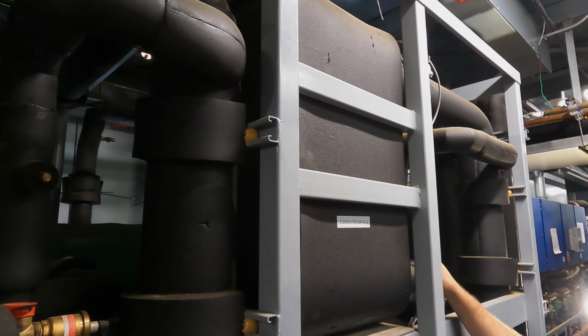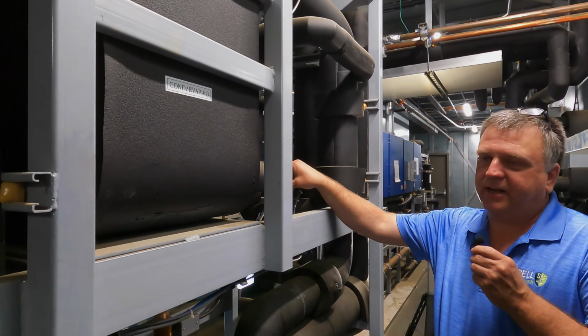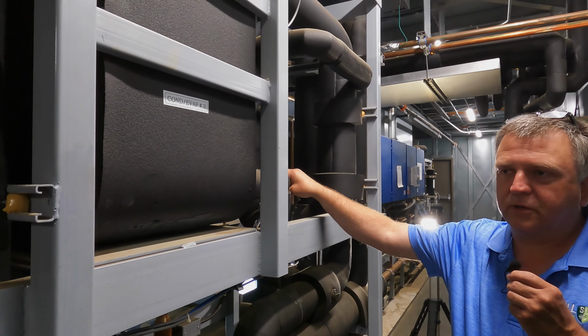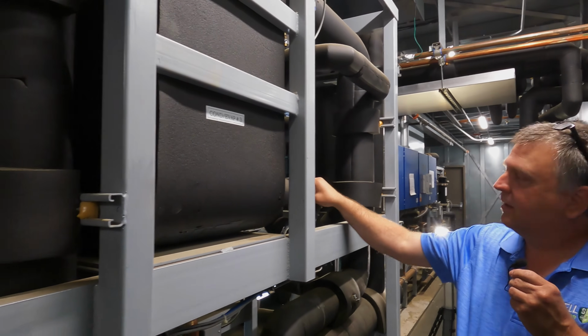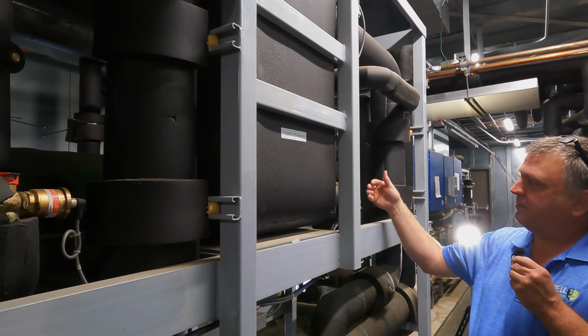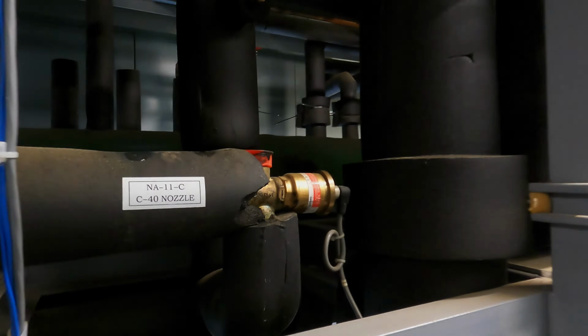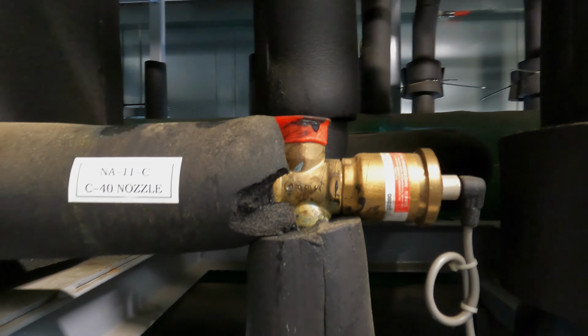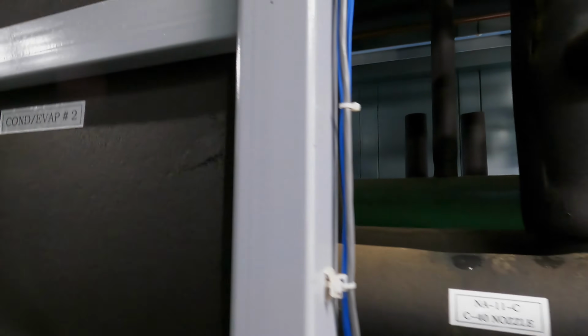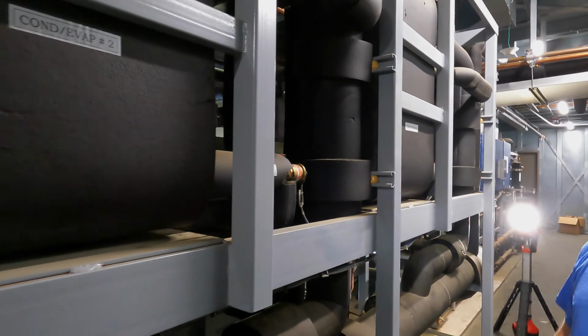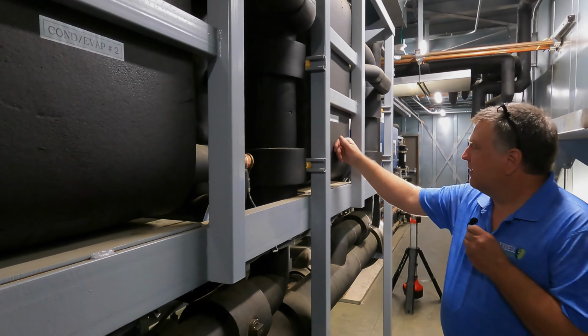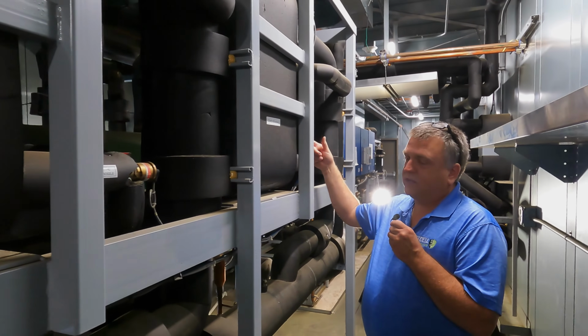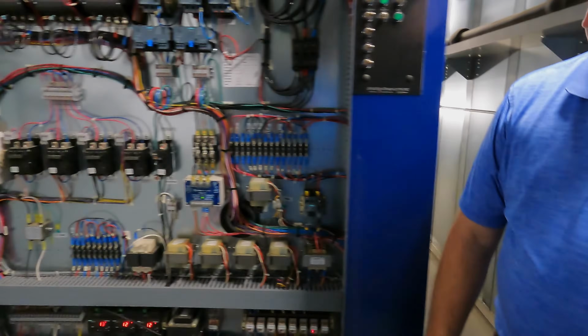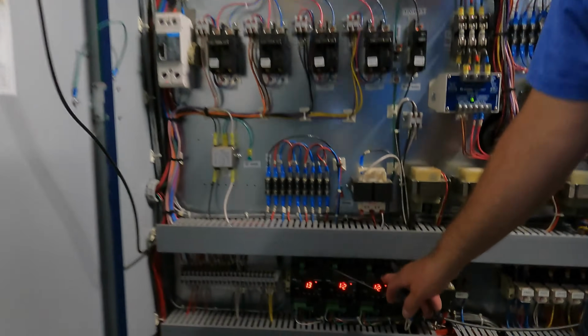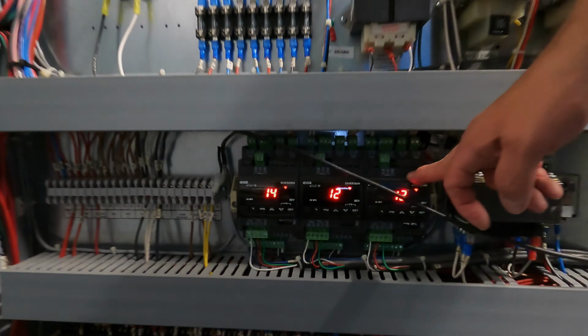Basically, one side of the chiller is our CO2. This side's going to be our 449A, and these modulating valves are controlled through an XM controller inside the rack. We're basically just modulating how much this valve opens to feed our condenser evaporator. It's called a condenser evaporator because it's the condenser for the CO2 compressors, and it's the evaporator for our vessel to change state. These valves are controlled by the XEV superheat controller.